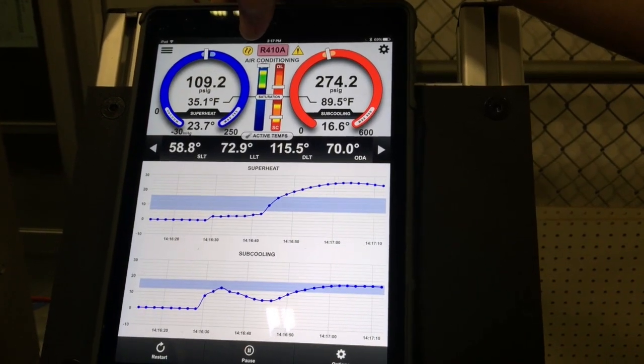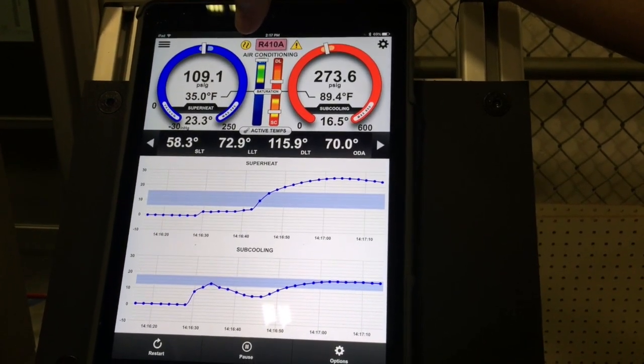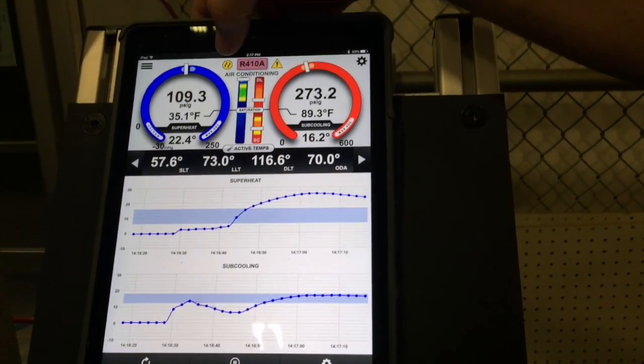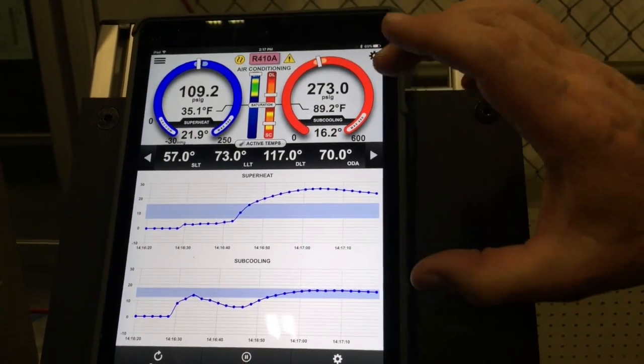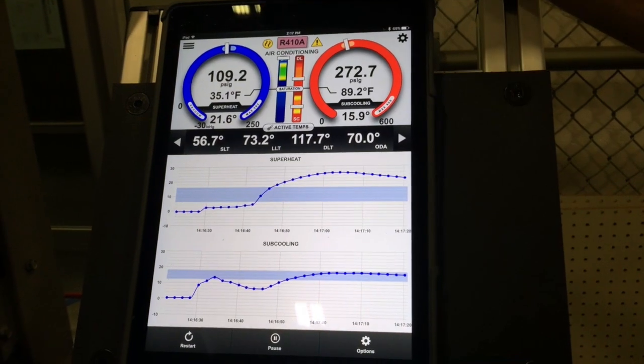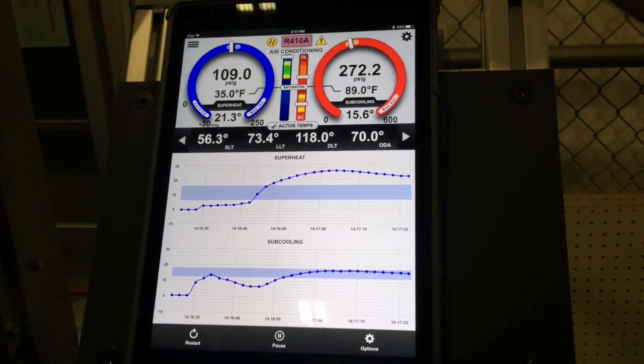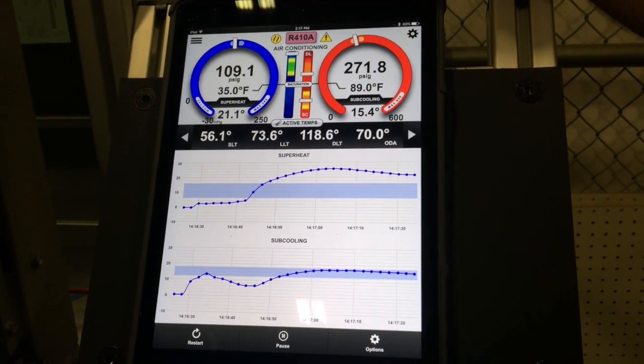It's not uncommon to see this kind of stuff happen. When the system first started, the liquid line temperature was stable, the suction line temperature was stable. I had this sort of reading here. Now they went out of stable again, and we have to wait till it restabilizes before we make our readings.